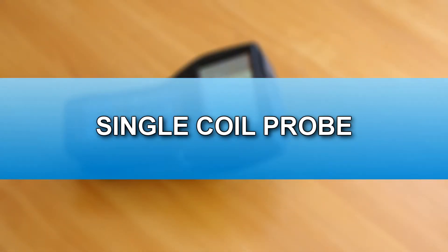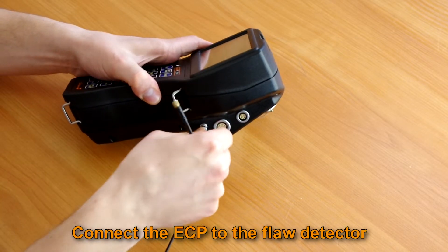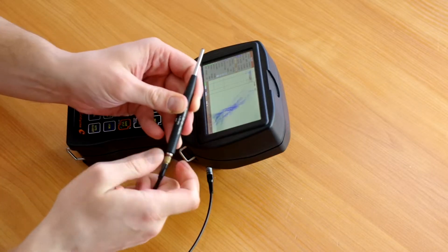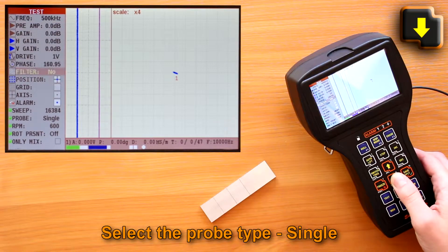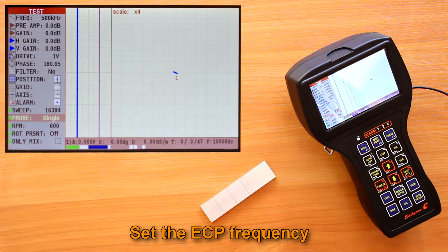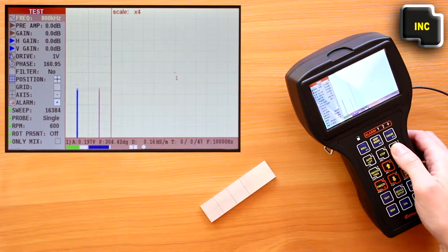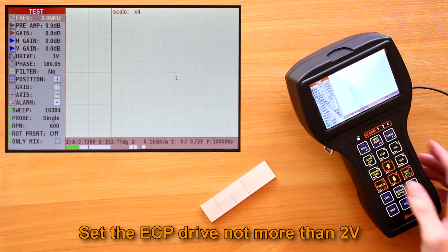Single coil probe. Connect the ECP to the flaw detector using a connecting cable. Select the probe parameter in the test menu — single type. Set the ECP frequency in a range specified in the registration certificates of the ECP; it can also be specified on the probe marking.